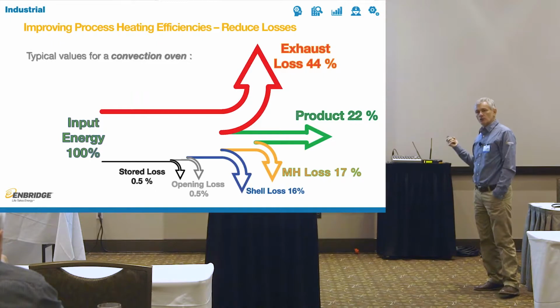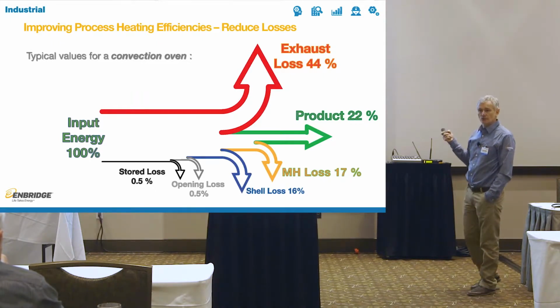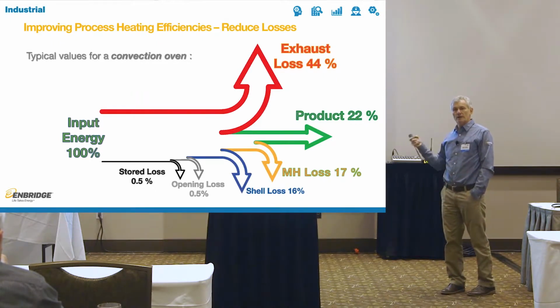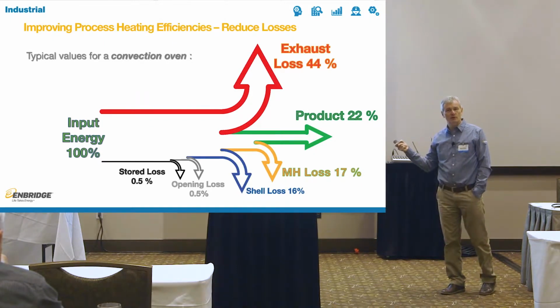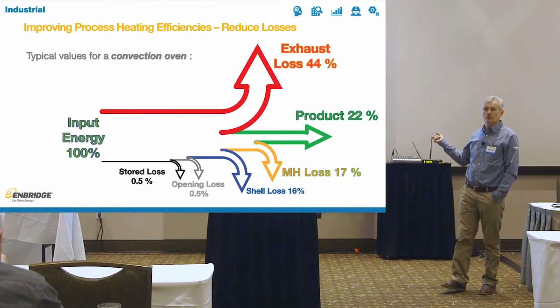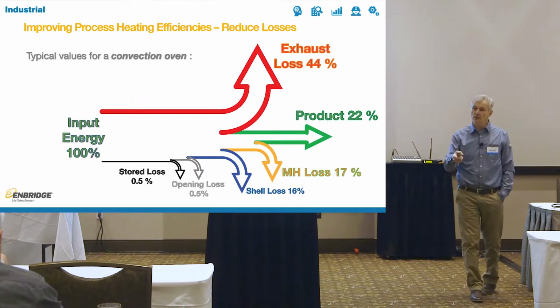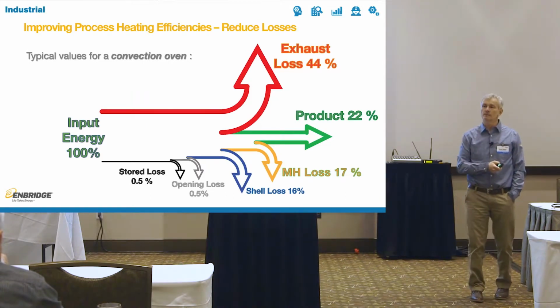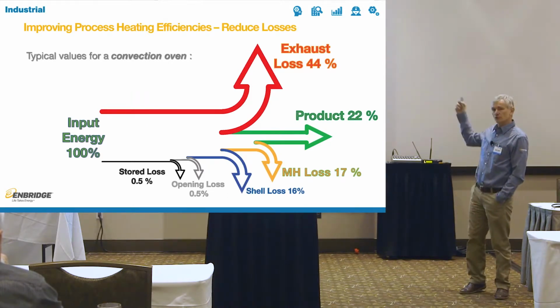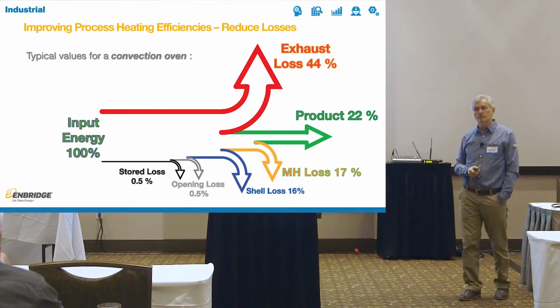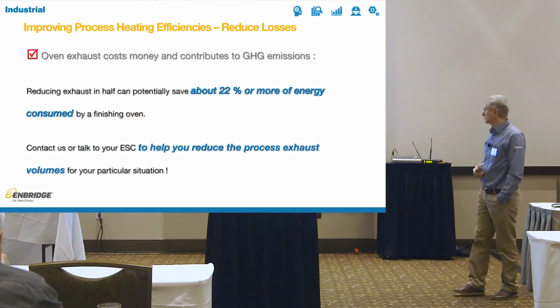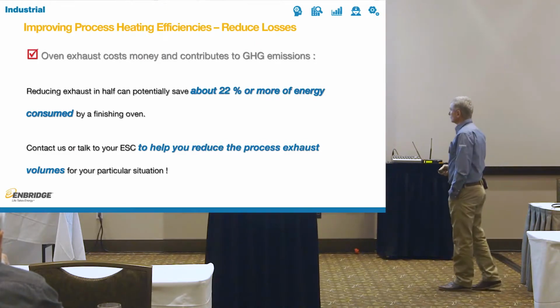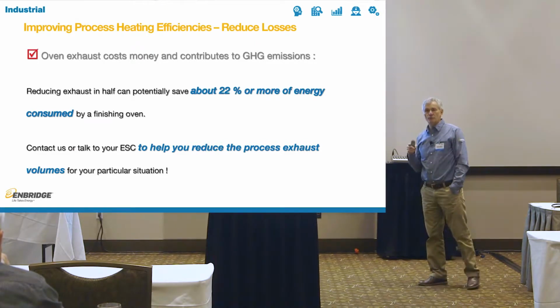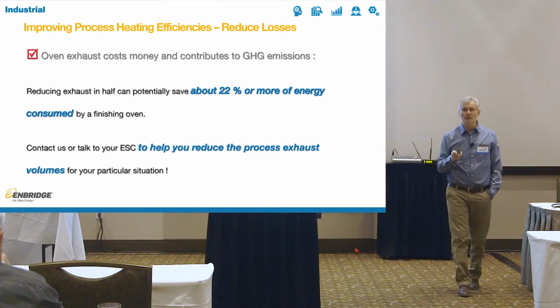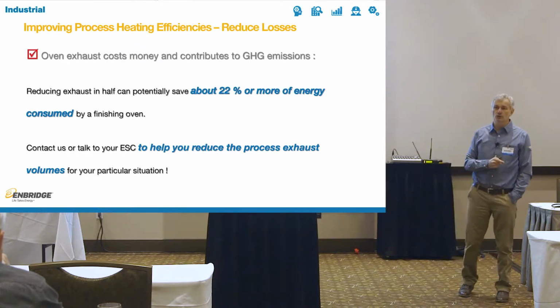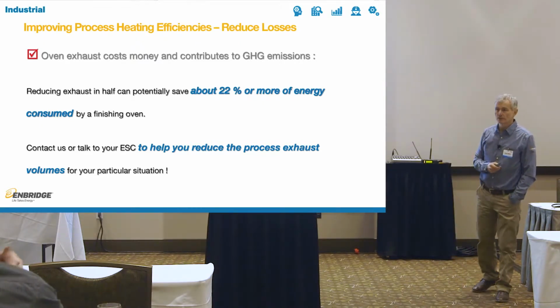What goes into your product is only 22% of your investment. Every $100 that you put into the oven results in $22 worth of value. Or to look at it the other way, you only need to spend $22, but you're spending 100. And 44 of those dollars goes up the stack. So even if you reduce it only by half, you save 22% of the energy going into your oven.